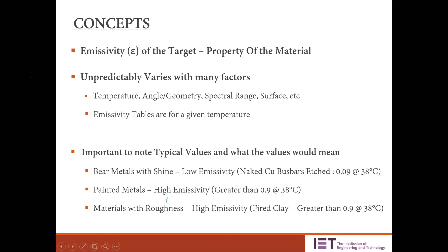And when the target temperature increases beyond 38 degrees, there is no telling how the emissivity would vary. So like I said, using emissivity tables is not a good idea. It's actually a very, very bad idea, and you should not be using them.